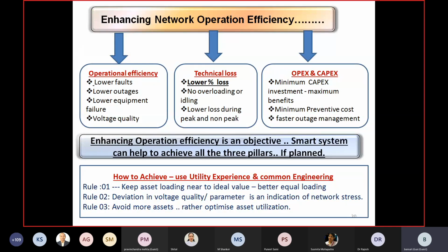When I talk about network operation efficiency, I am talking about operational efficiency. That means fewer faults, fewer outages, fewer failures, and good voltage quality. Of course, technical losses need to be lower, and operational and capital costs need to be lower. Based on this, we have made certain formulas, or what I call apps, or logics: if I keep my asset loading near the ideal value and keep all asset loading equal, then I will have the best operational efficiency, lowest technical losses, and lowest OPEX and CAPEX, because failures will be lowest, there will be no overloading, and assets will be used most efficiently. So my need is operational efficiency, technical loss, and OPEX and CAPEX.